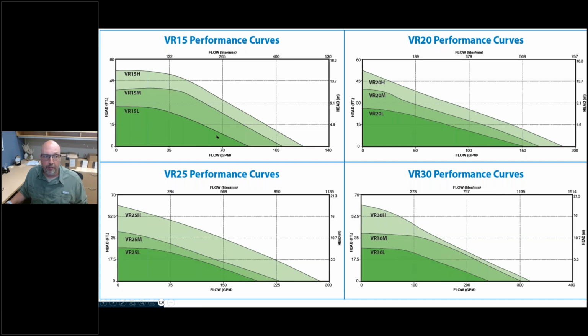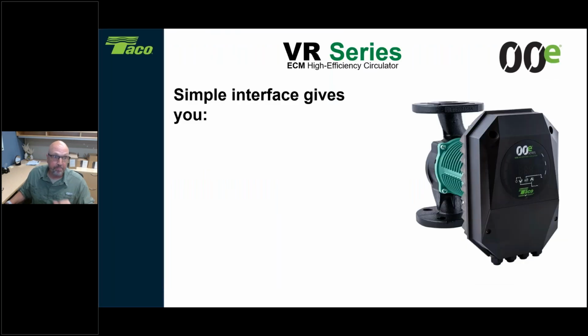The 15L will have a little bit more rangeability, so to speak. Very small changes in the speed of that circulator also have very small changes in its flow and head. But meanwhile, you put the 15H in there, small change in speed, drastic changes in the flow and head that it gives you. So just watch how you're designing and selecting some of those circulators that you have out there. We're not going to go through sizing and anything like that today. I want to talk about how we start setting these things up today. So, a little bit of review from last week.